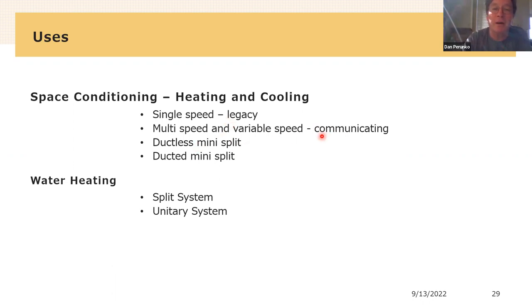Under that sort of communicating commands, instead of being like 6 or 8 wires that are on-off commands, there's 2 or 3 wires, and they use a pulse command strategy. And so the circuit boards are using a pattern of electrical pulses to talk to each other, and there's nothing that an installer can do with it. You literally just connect a 2 or 3 wire lead onto one machine and then to the other machine, and then that's it, right?